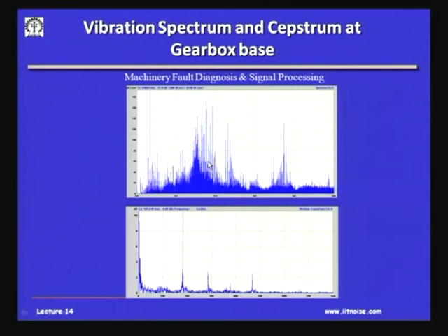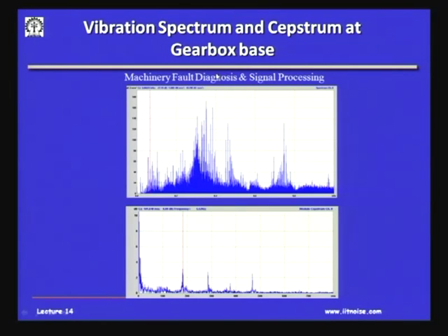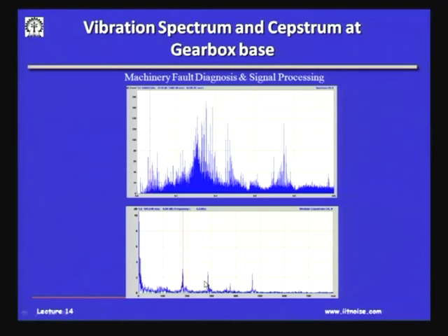And that is how Cepstrum helps us identify signals, helps us find the important frequencies in a spectrum. Okay. The effect of the path, etcetera, is lost, because if you look here at the gearbox base, a lot of effects of the path were there. The gearbox base was loose. In fact, we had discovered many loosenesses in the gearbox foundation itself, and all those effects are nullified once you do the Cepstrum. Those effects can be easily removed.